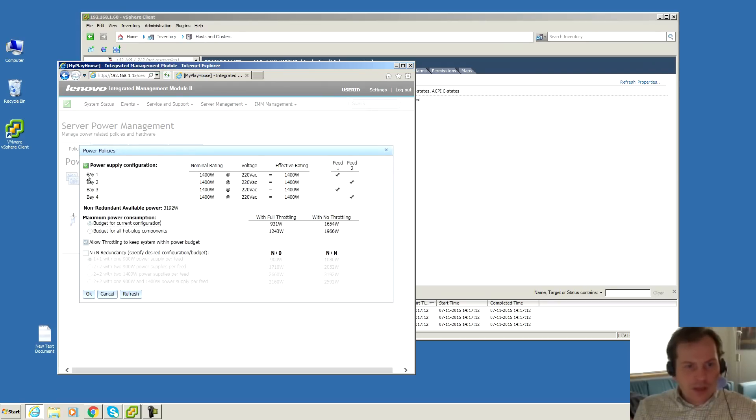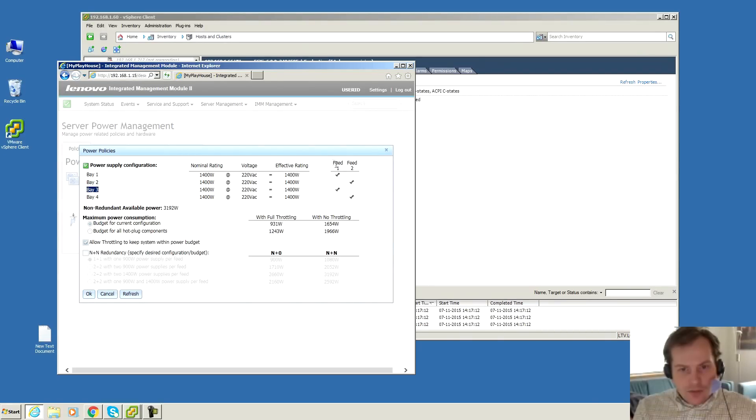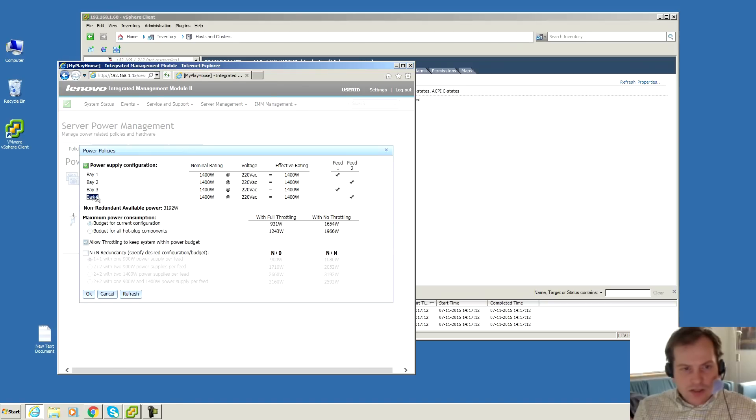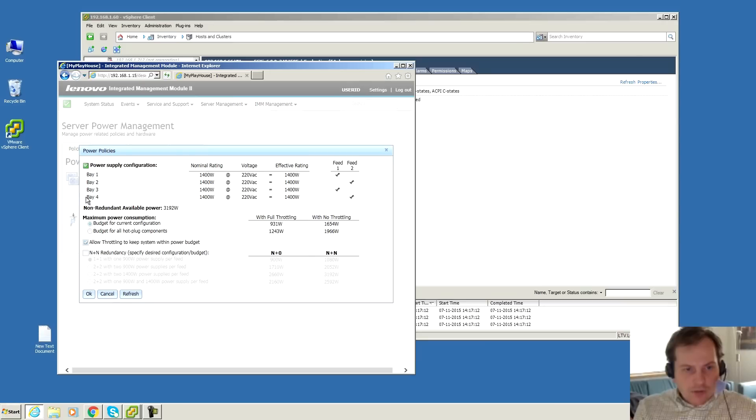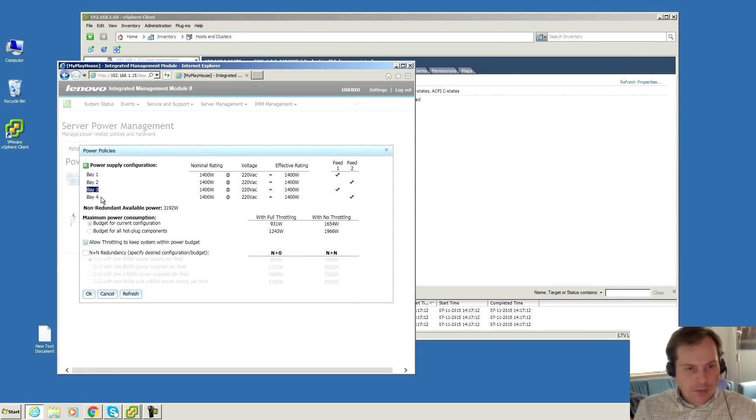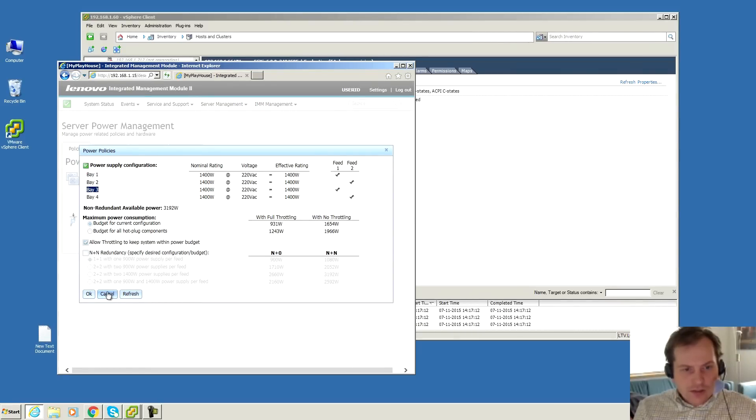I just unplugged one power supply at a time and nothing happened. In here there are different possibilities. It looks like bay number one is connected to bay number three and they make something called feed number one. There is also a feed number two which is bay number two and bay number four. I have not been altering on these settings at all.